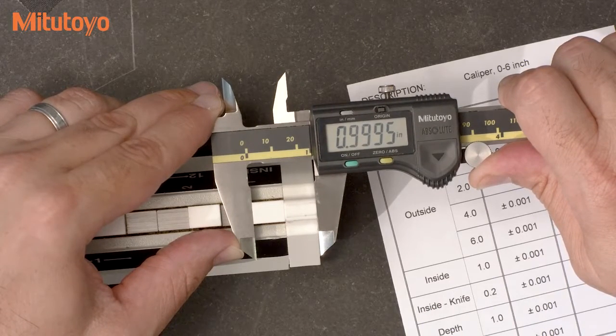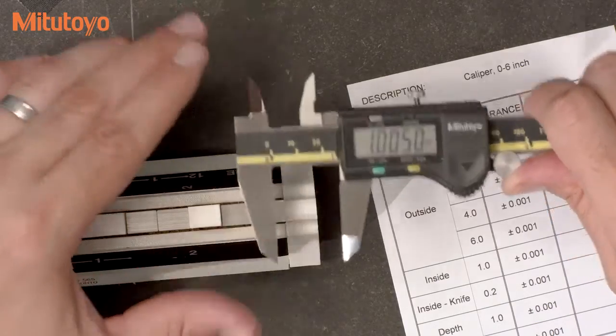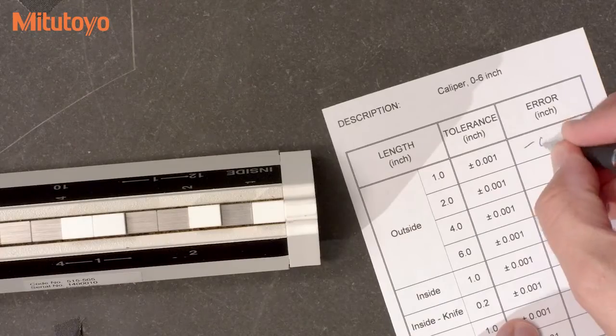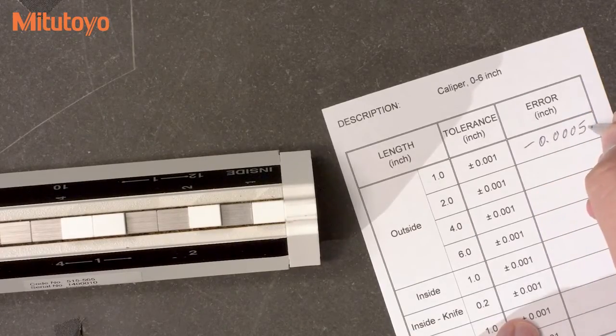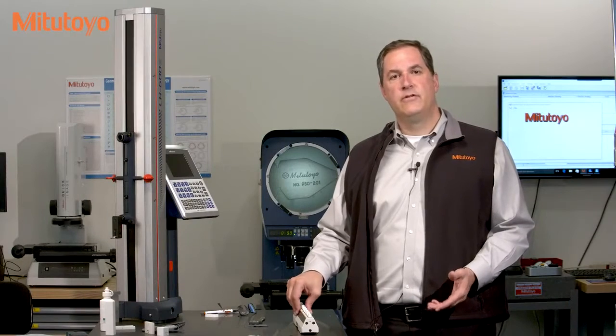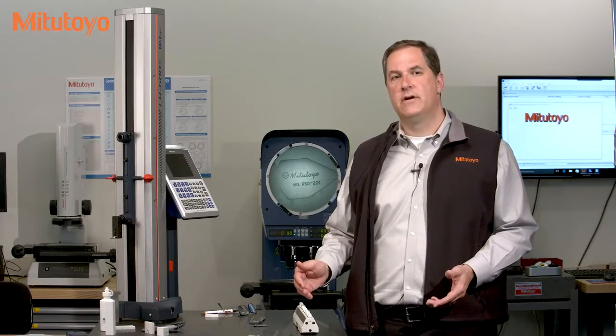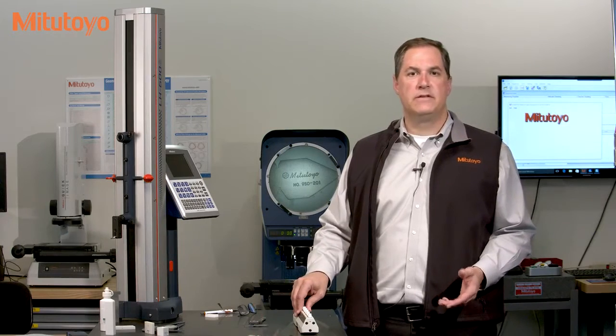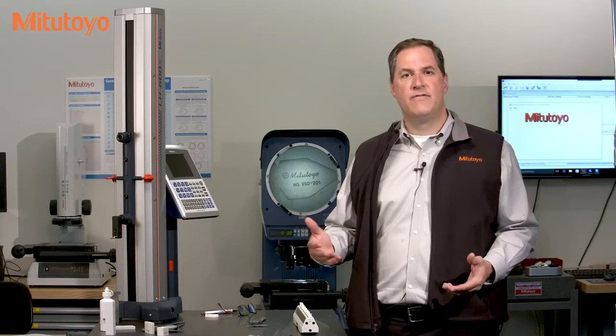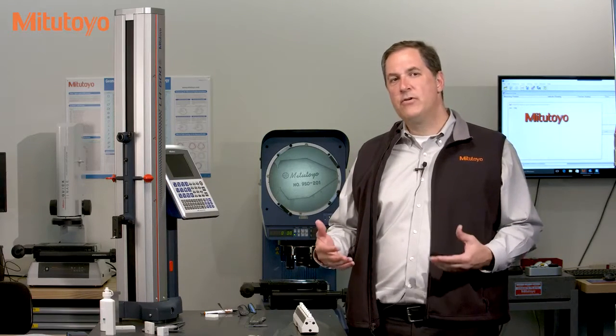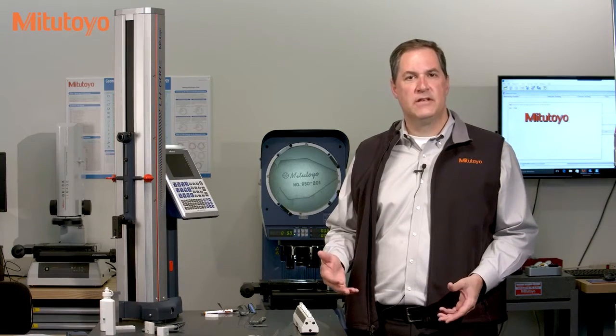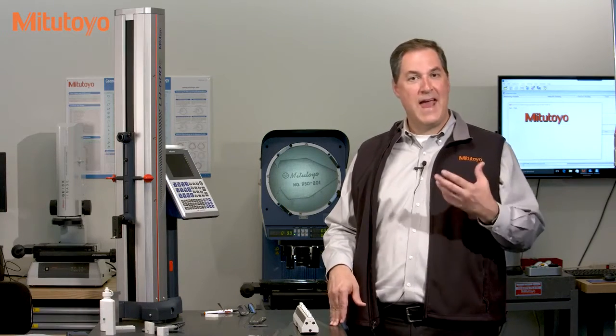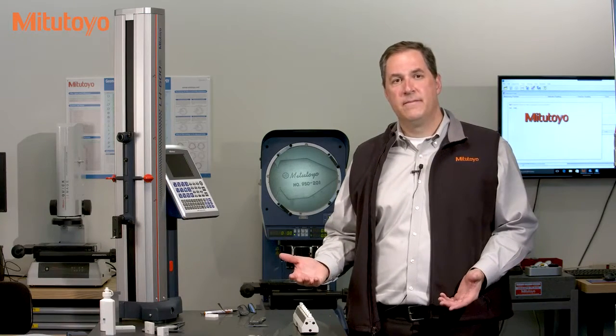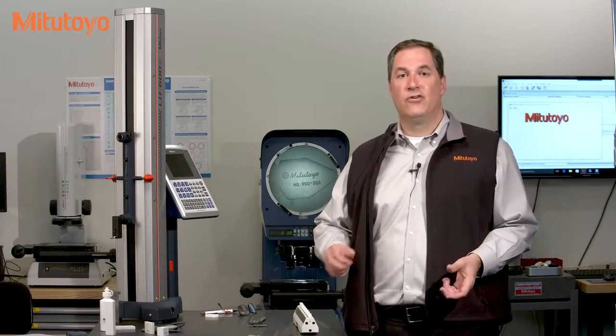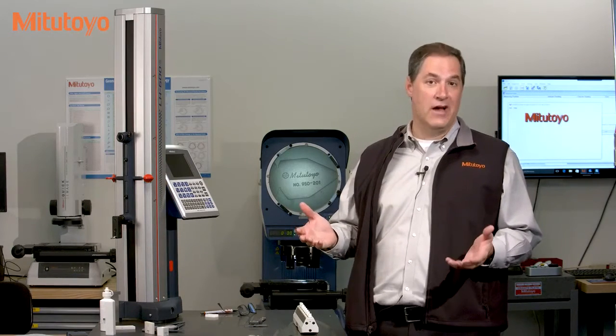It looks like the error at this test point is -0.0005. So I'll write that down. It's understood that when using a caliper, you need to rock it around a bit to get the proper result. This applies to normal use as well as in calibration. It's not correct, however, to take a bunch of readings and report the average values during the calibration. The caliper should be repeating within the specification limits for the length accuracy. And if not, then the caliper should be rejected. It is also not correct to rock it around until you get the value you like, right?